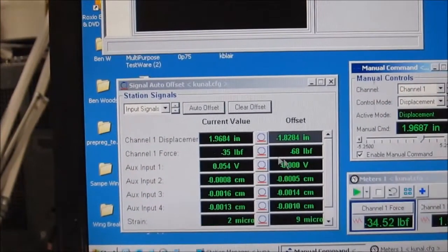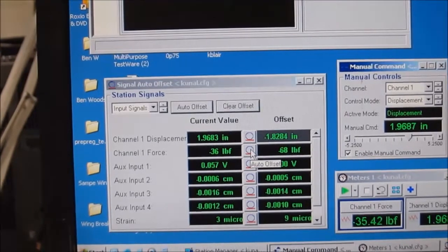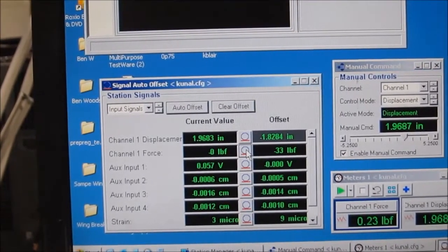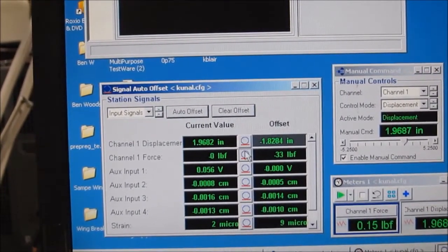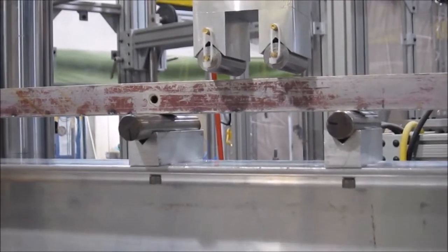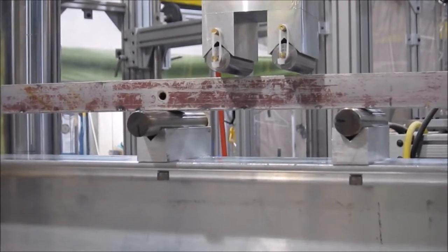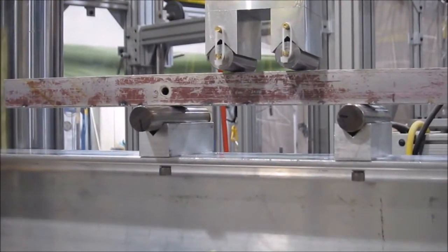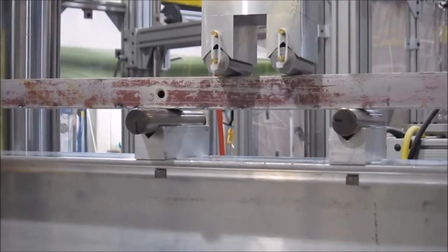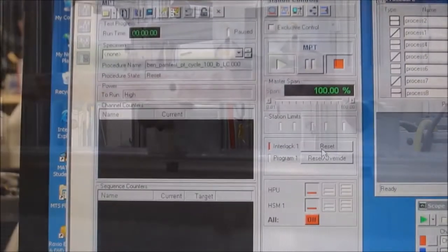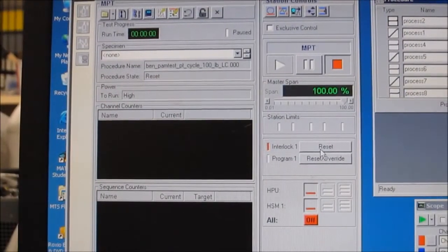Use the force offset button to get rid of any pre-stress that is artificially induced by clamping. Lower the actuator onto the piece and make sure there is no more pre-stress again. Offset the force and displacement.